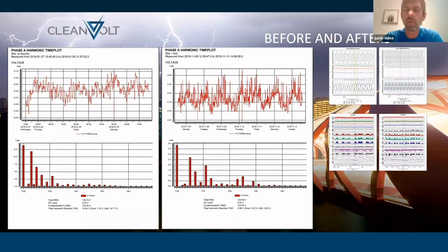But what we found over the years is that harmonics are typically generated a few different ways. Mainly they're generated by the electronics that are running, and depending on what it is that's operating, they will create a harmonic. But what we're finding is that when those harmonics and the energy surges come back to the power source and start to mingle and interact, it can create what we're calling a phantom harmonic. In this case, we know the third order of harmonic in the before test was a phantom harmonic because no equipment should be emitting that order of harmonic.